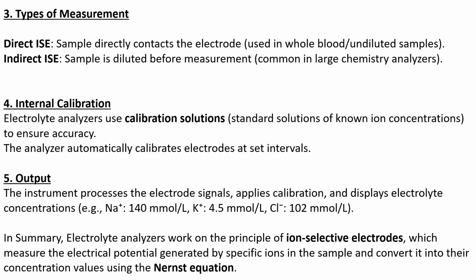Types of measurement. In direct ISE, the sample directly contacts the electrode, while in indirect ISE, the sample is diluted first before the analysis. Internal calibration. Electrolyte analyzers use calibration solutions, which are standard solutions of known ion concentrations, to ensure accuracy. The analyzer automatically calibrates electrodes at set intervals. The output. The instrument processes the electrode signals, applies calibration, and displays the electrolyte concentration.